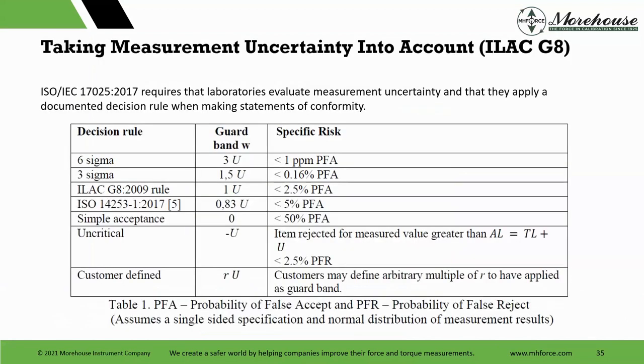So taking measurement uncertainty into account, here's ILAC G8. It's a free document. You just type in ILAC G8 2019. You can go download it. You can work through it. But here's some different guard bands. Decision rule, 6 sigma, 3 sigma. ILAC G8 2009. I like that rule. That's less than 5. ISO 14253, I believe you have to buy that standard. Simple acceptance. Talked about that.